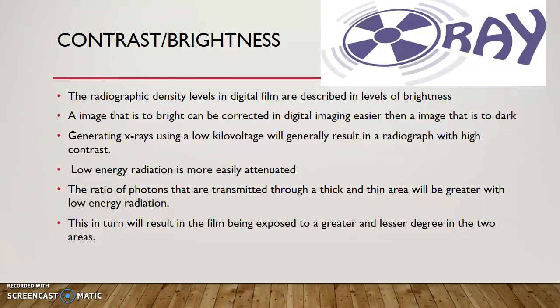Contrast, continued. Low energy radiation is very easily attenuated. Generating X-rays using low kilovoltage will generally result in radiographs having too high contrast. This in turn will result in the film being exposed to a greater and lesser degree in two areas.